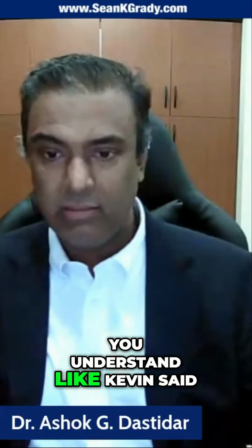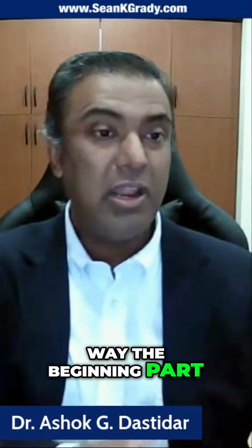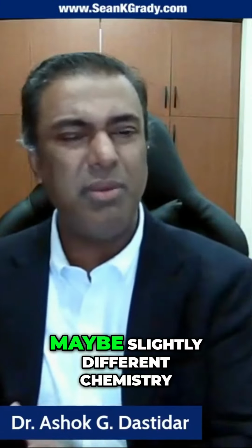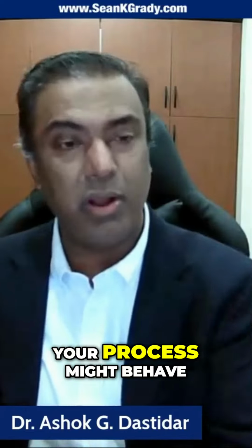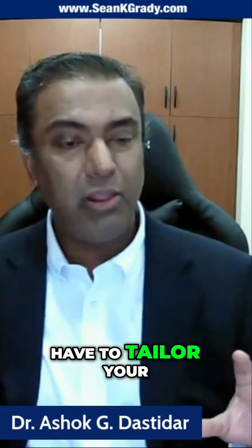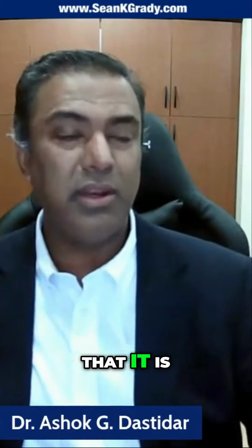and then you test to make sure that you understand, like Kevin said, that maybe at the beginning part of your process your dust behaves one way, but your dust is a different particle size, different moisture, maybe slightly different chemistry towards the end of your process, and might behave in a completely different way. So you're going to have to tailor your protection and mitigation systems depending on the combustibility and reactivity of the dust that you're dealing with in the form that it is.